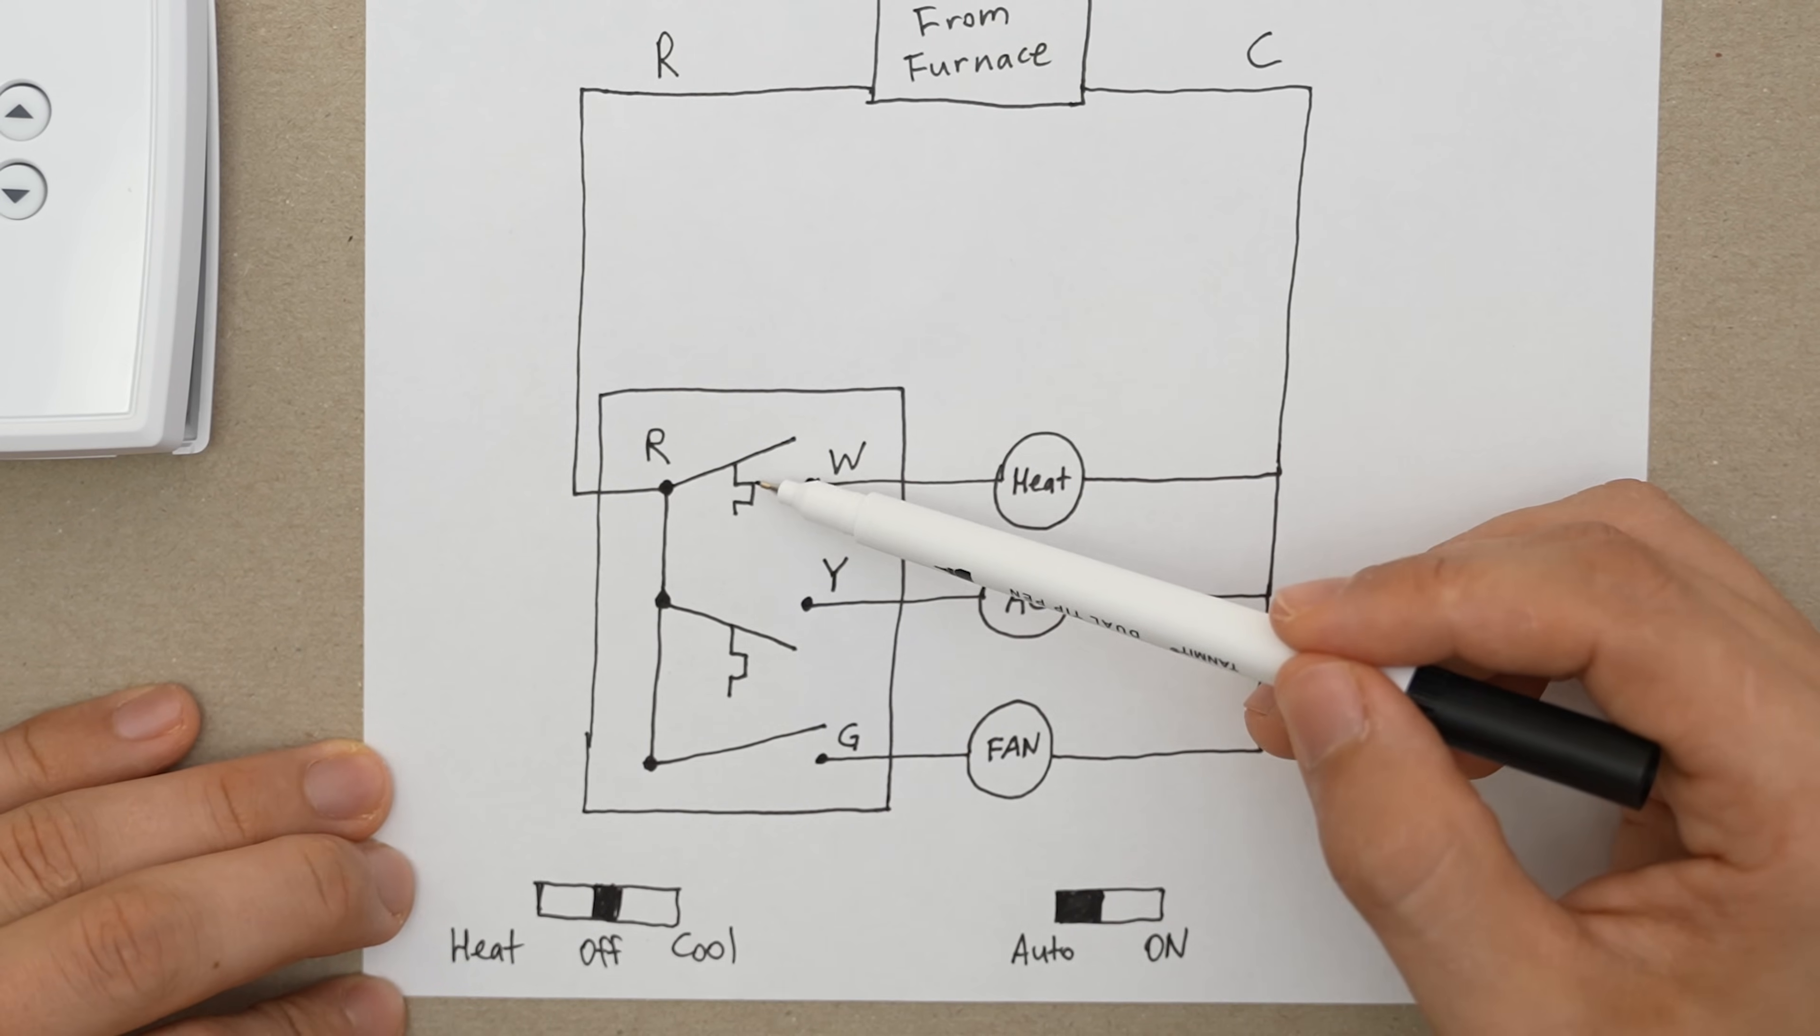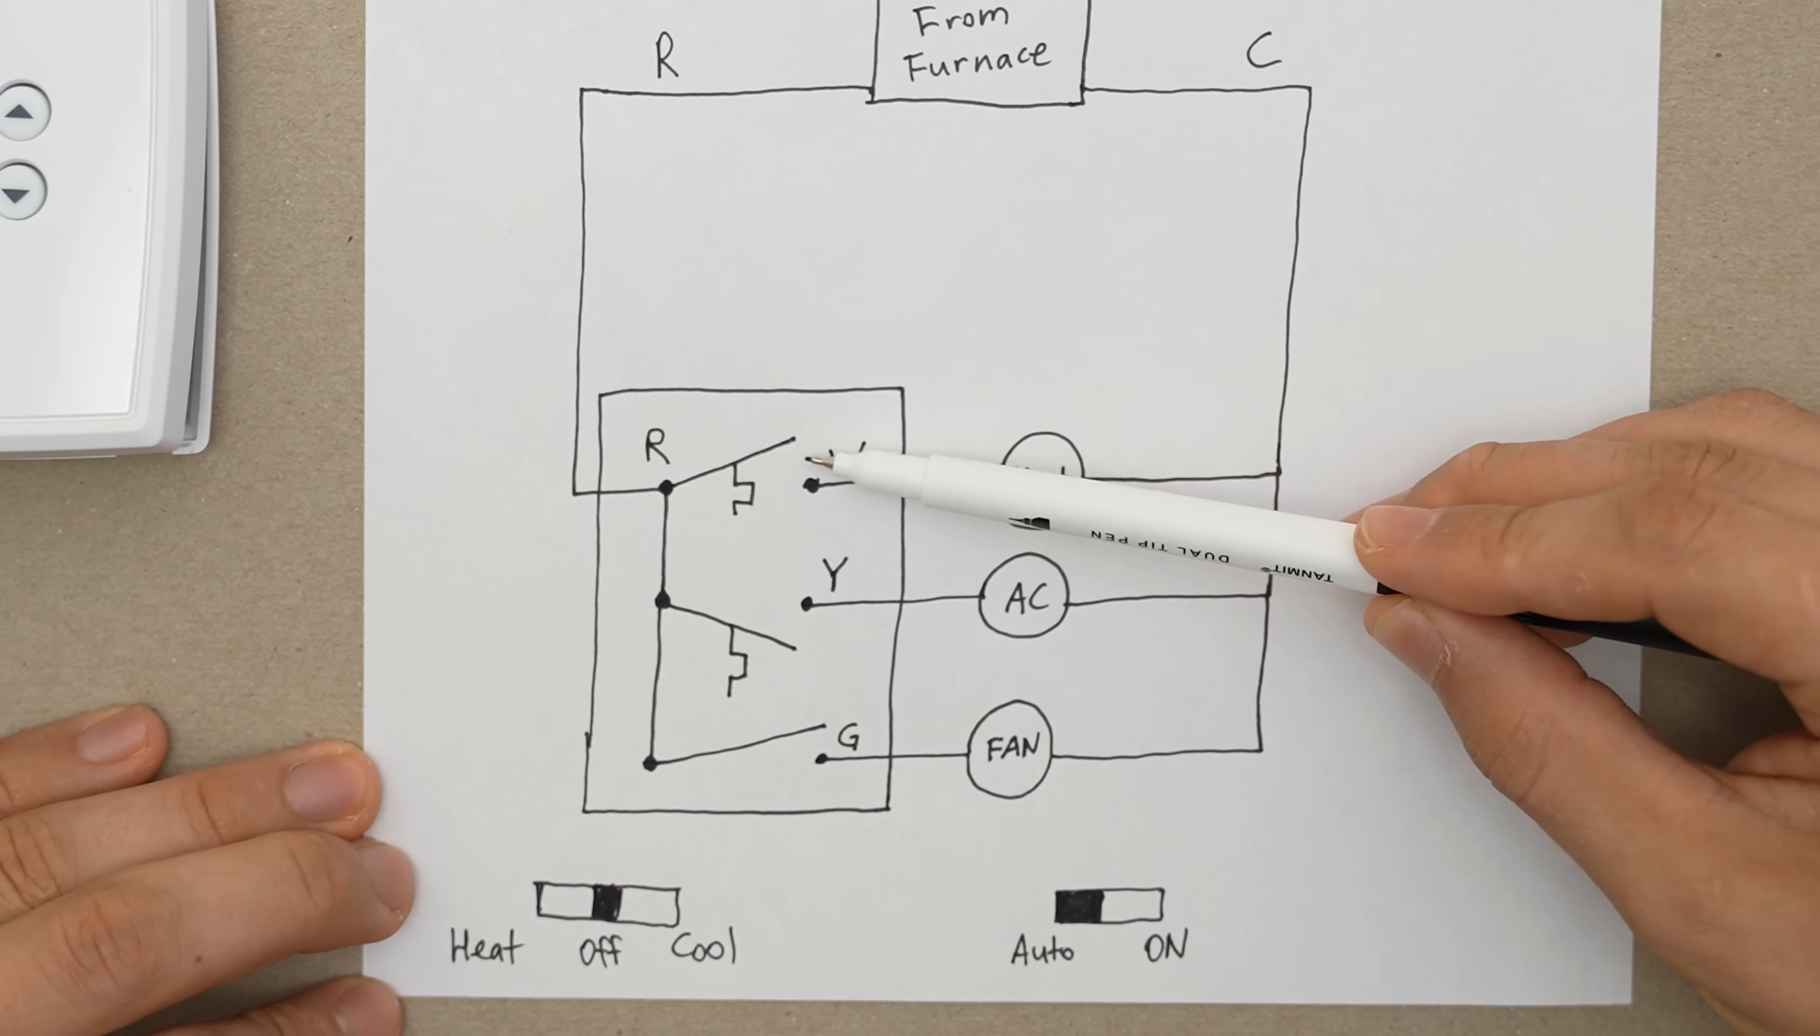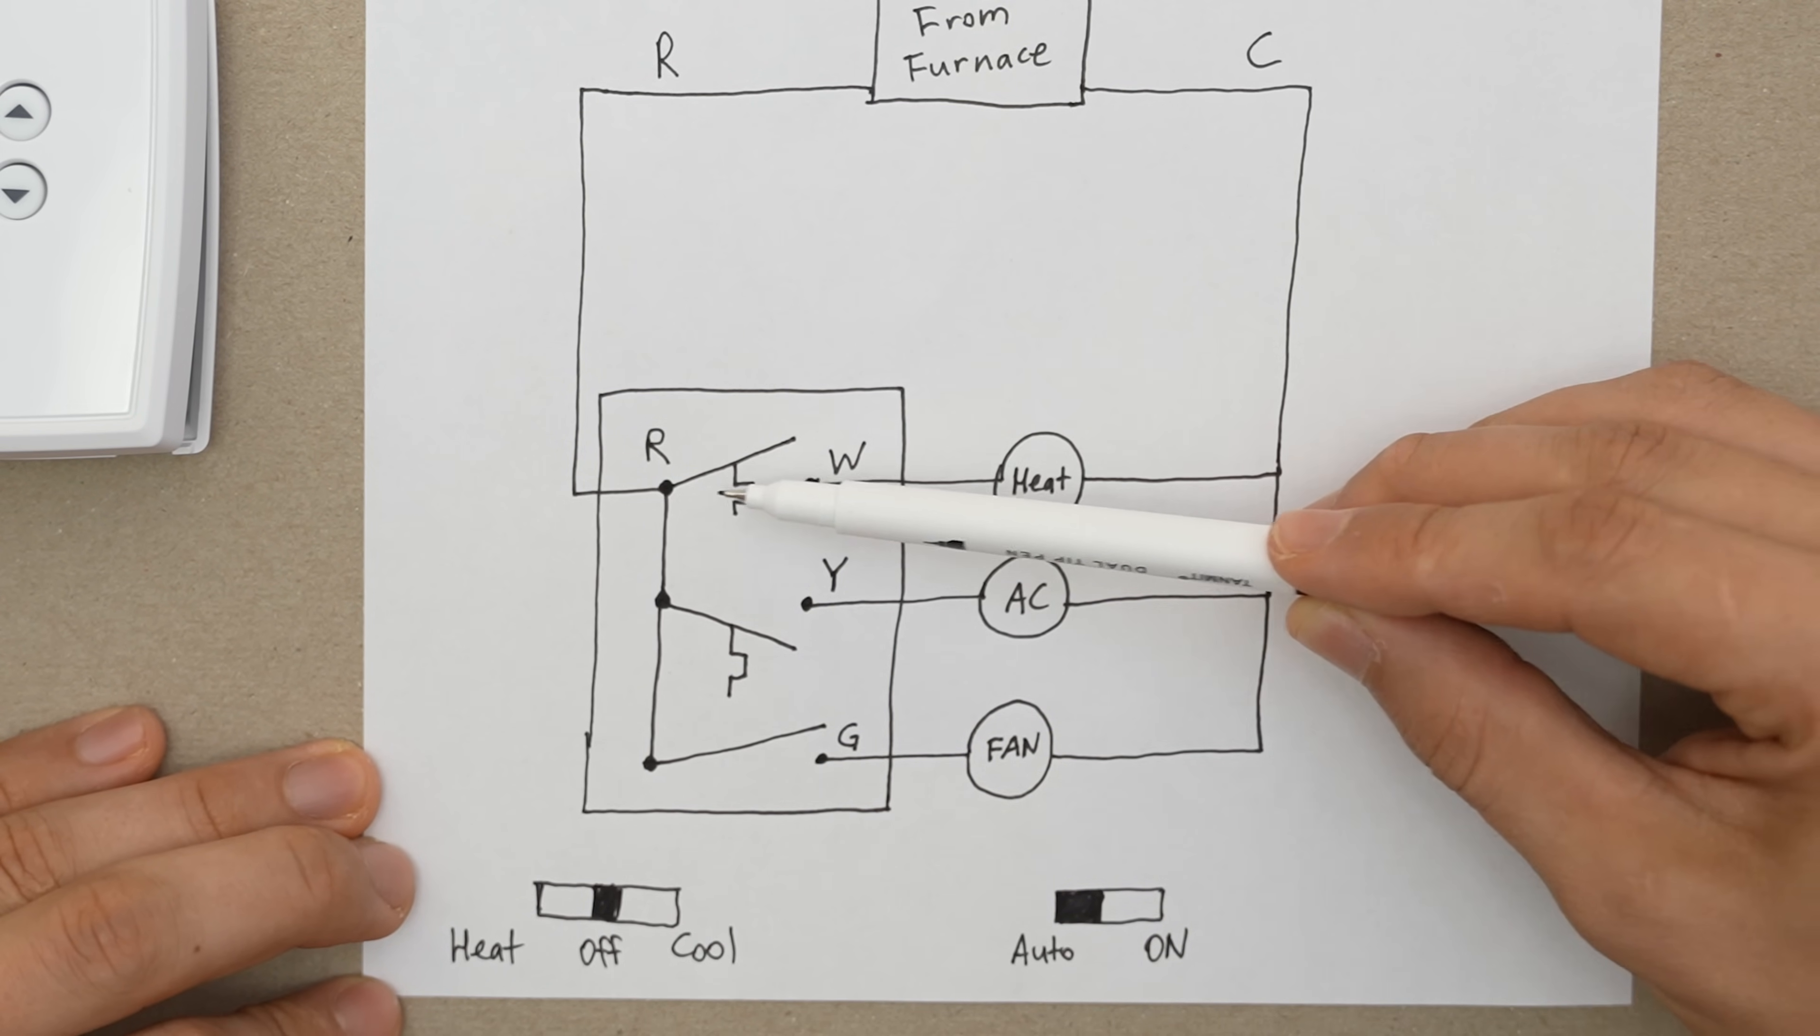And let's get back to these switches for a little bit. The way these switches work is they're measuring the temperature around the thermostat. So let's say that the temperature inside of the house is 75 degrees, and you have your heat set to 72. So what that means is, since this switch rises when the temperature rises, if the temperature in the house is 75, this switch is going to be in the risen position, or basically it's going to be open. And if your thermostat is set to 72, as the temperature in the house starts to cool down, let's say it's winter outside, it goes down to 74, 73, 72, 71.